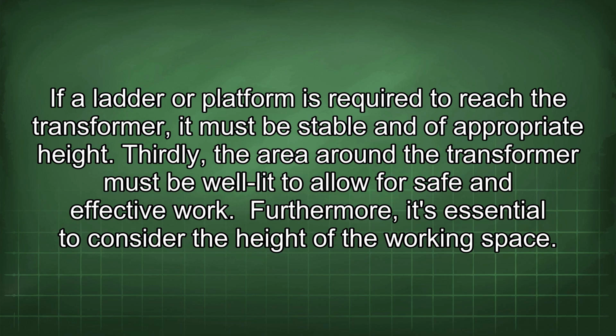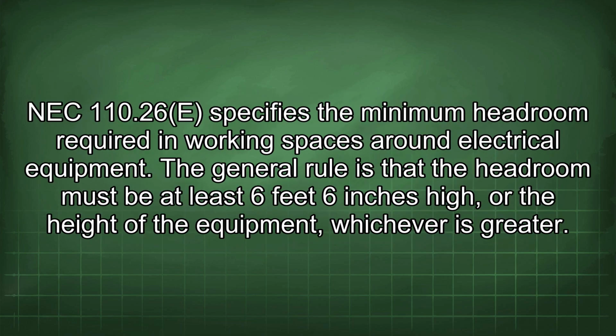Furthermore, it's essential to consider the height of the working space. NEC 110.26(E) specifies the minimum headroom required in working spaces around electrical equipment. The general rule is that the headroom must be at least 6 feet 6 inches high, or the height of the equipment, whichever is greater.